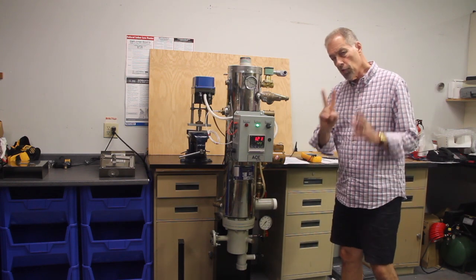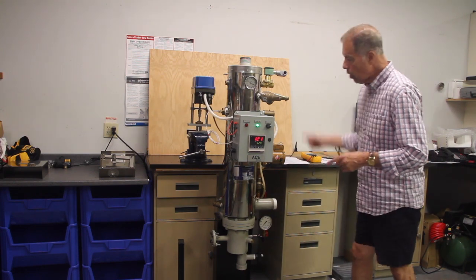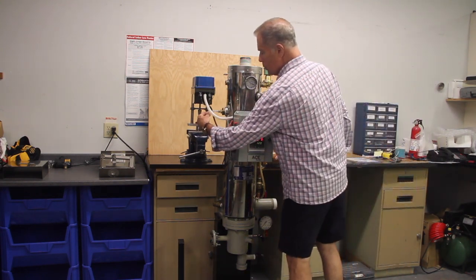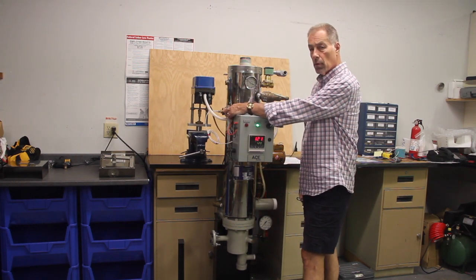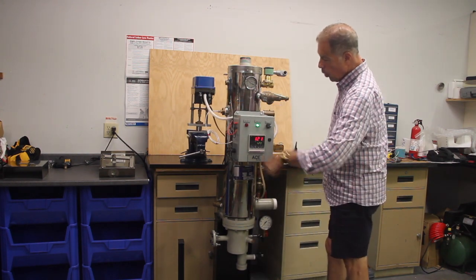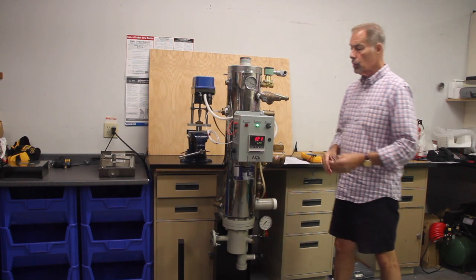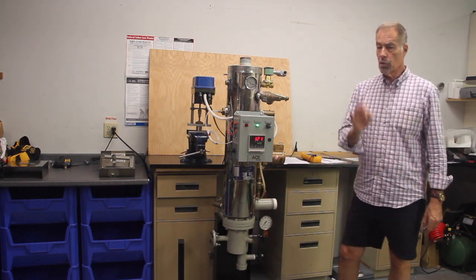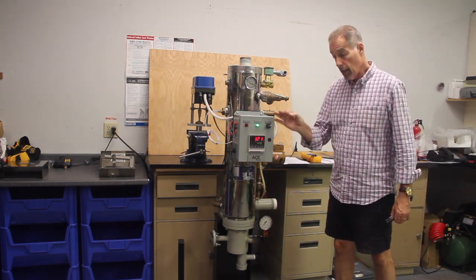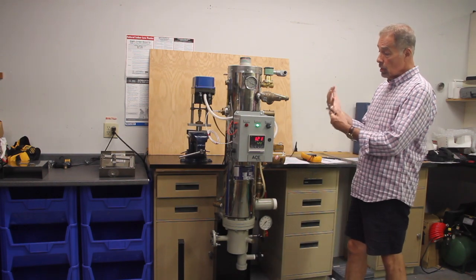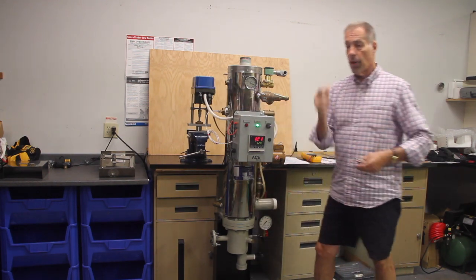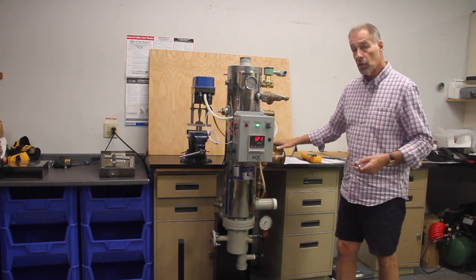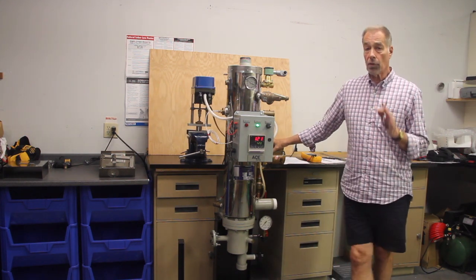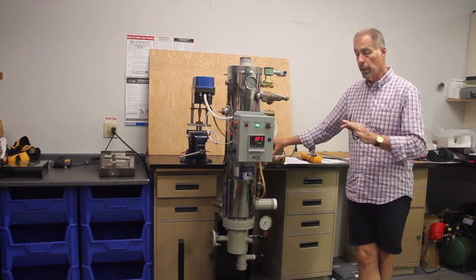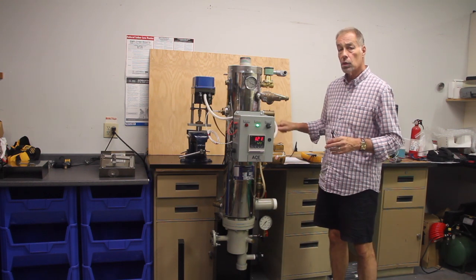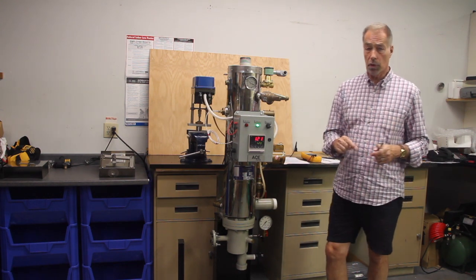Its job is twofold: to keep the water always washing over the temperature sensor. This is your temperature sensor here. We need water always washing over that sensor so we know exactly where the temperature is, or it needs to be. So as the load changes, we want this sensor to pick it up right away. And if this pump doesn't work, we're not going to have good temperature control. We'll talk about that when we get to the maintenance part, but if you lose this pump, you're going to have very poor temperature control.